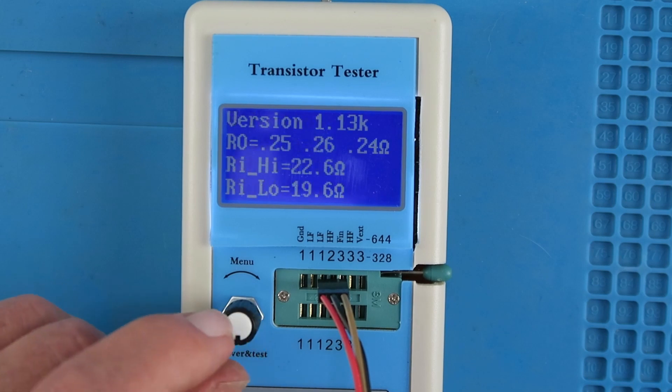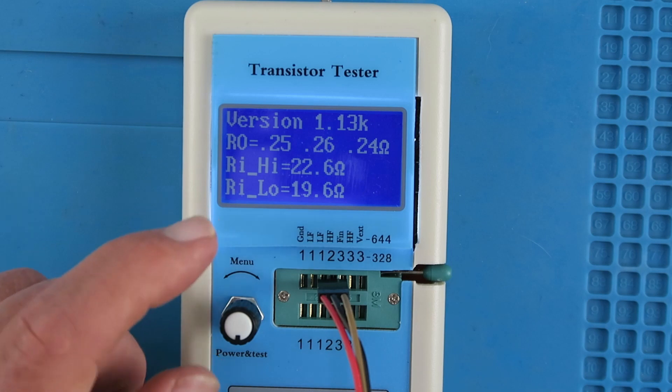The show data option gives us the version of the firmware in use and the values that were detected when the self-test was run to calibrate the unit.